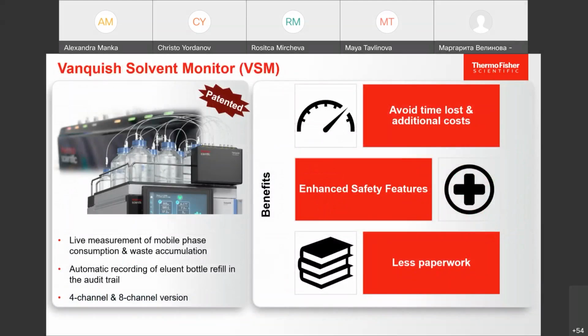And then, as already mentioned, the Vanquish Solvent Monitor, which has patented technology. It really measures the live consumption and waste accumulation while the system is running. So it's not only software driven, but a real measurement. And it also records in the audit trail when the eluent bottles are refilled. And we have a 4-channel and 8-channel version. So this really avoids time lost and additional cost.